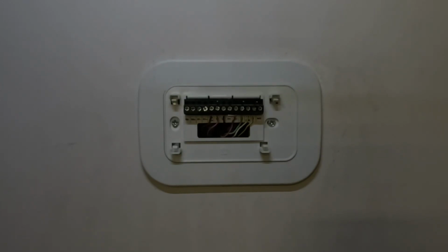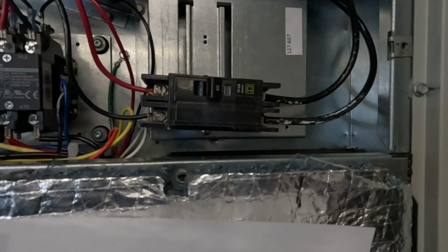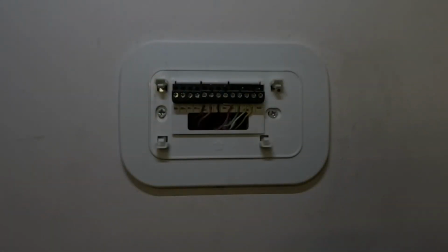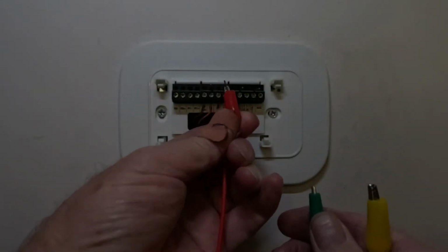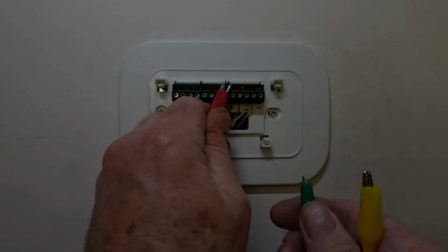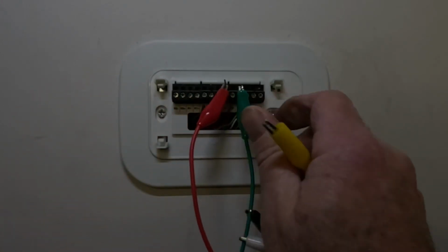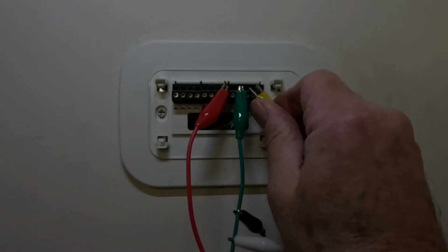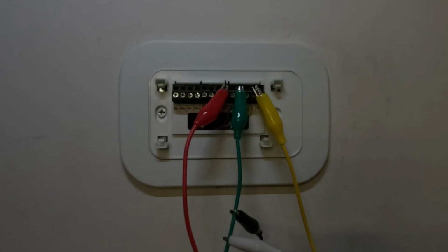Inspect the wires at the subbase to ensure they are not stripped too far back, shorting out against the metal electrical box or to each other. Turn on the breaker. Jumper the terminals at the stat subbase to test the stat wires. You can disconnect the stat wires at the subbase, or I use paper clips or small brads to do this. Does the unit function correctly jumpering all modes at the thermostat subbase?